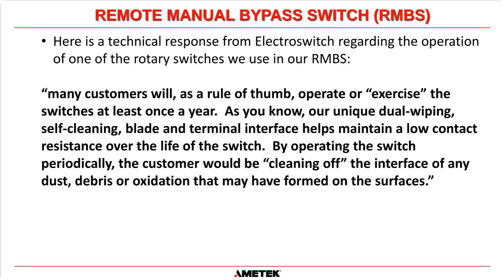The actual switch barrel that we use is from a company called ElectroSwitch in most of our RMBSs. And this is a direct quote from somebody who works for ElectroSwitch. They specifically state that many customers will, as a rule of thumb, operate or exercise the switches at least once a year. And they go on to say, as you know, our unique dual wiping self-cleaning blade and terminal interface helps maintain a low contact resistance over the life of the switch. So therefore, by operating the switch periodically, the customer would be cleaning off the interface from any dust, debris, or oxidization that may have formed on the surfaces.